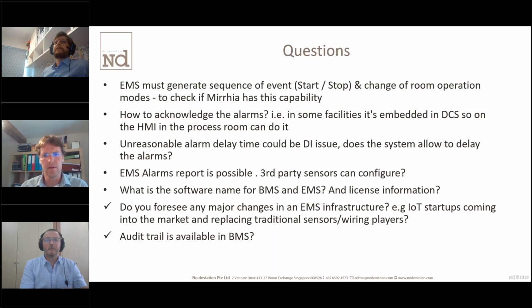And for me, that's really a good question, because it shows that the system is part of the control and the monitoring, but the commissioning and the capability of the BMS is what's going to lead you to increase delay, because you cannot recover fast enough. Yeah. So typically you can see that in terms of pressure, if your system cannot recover the pressure fast enough, people will tend to increase the delay of alarm. That's not a good practice, because you end up in this kind of watermelon situation, where everything looks great, you have no alarm, but actually you are not in control.